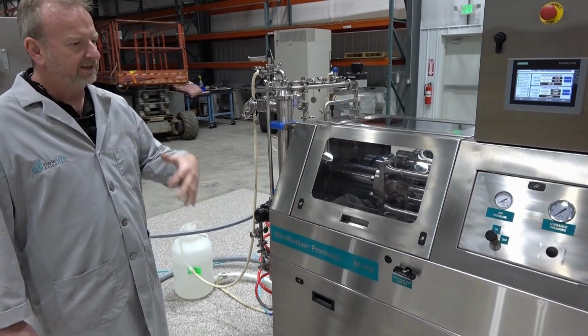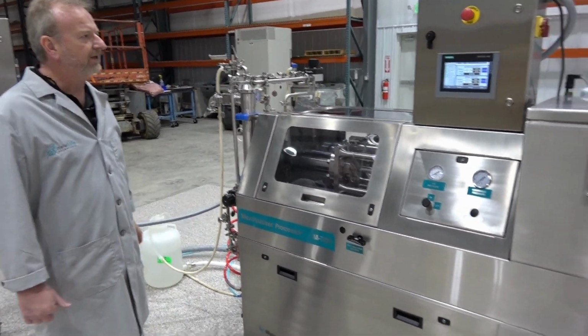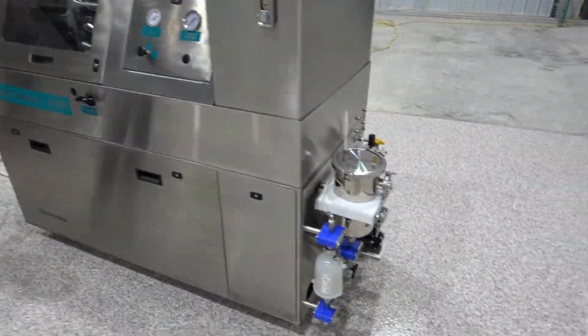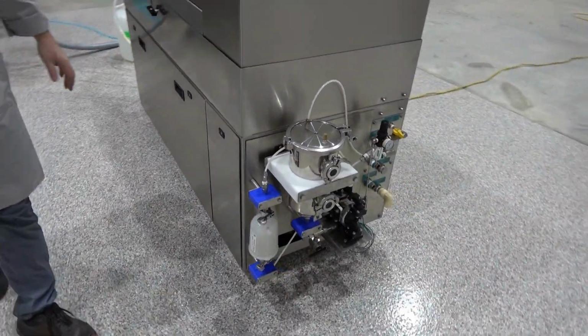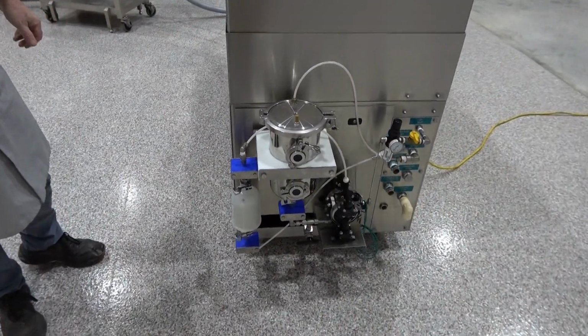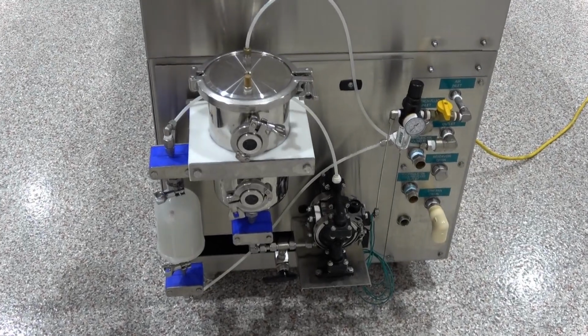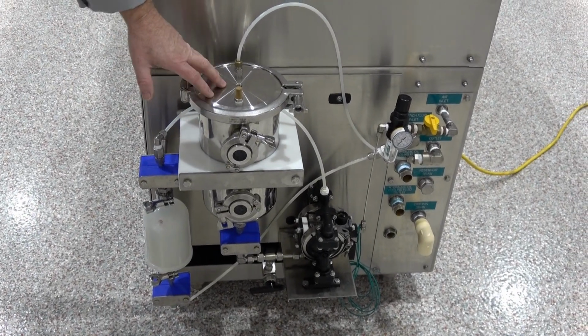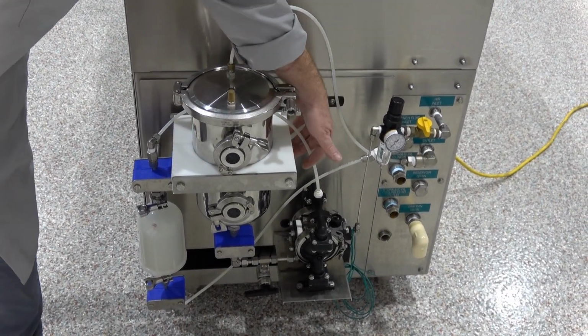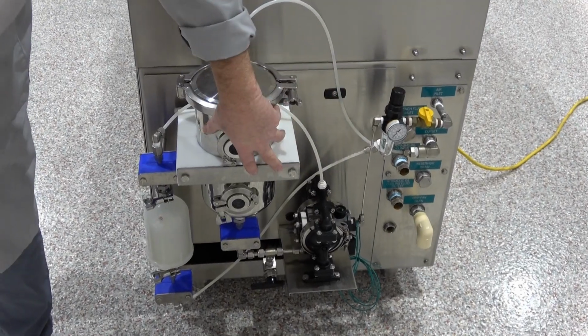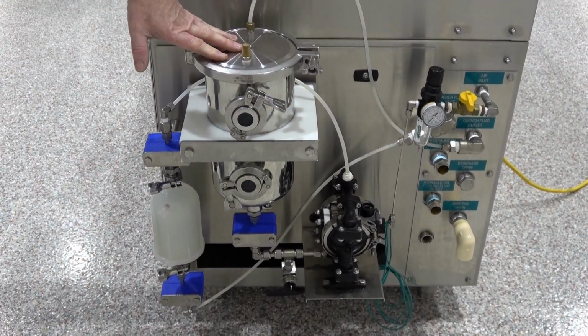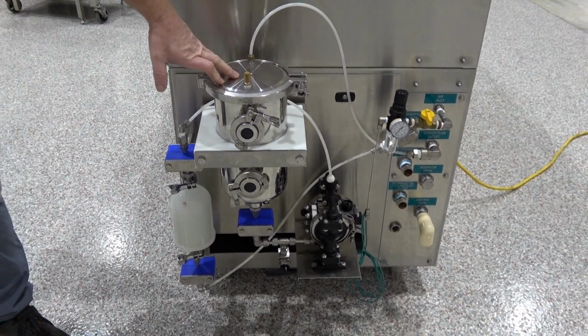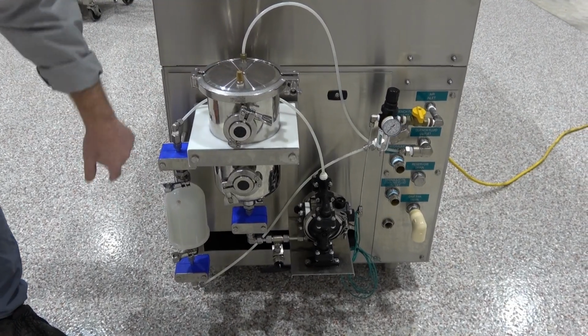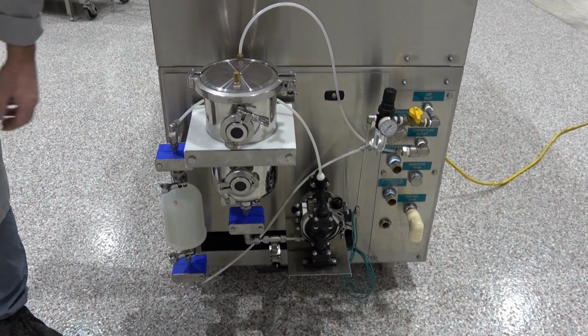The quench fluid system's already hooked up on this unit too, on the end over here. This is the quench fluid option that the manufacturer offers. It was installed with a little diaphragm pump, and all it does is recirculate your quench fluid, normally deionized water, refiltering it as it comes back through and recirculating it.